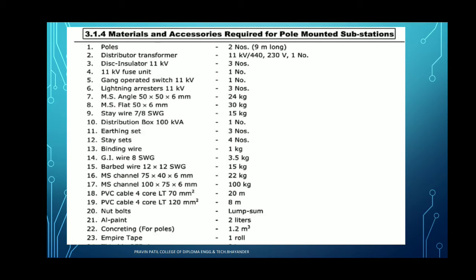mounted substation. In a pole mounted substation, two poles are required. Two 9-meter long poles are required in the pole mounted substation. Then the distribution transformer, 11 kV by 440 volt or 11 kV by 230 volt. One step down distribution transformer is required in a pole mounted substation, and the length of that pole is about 9 meters.